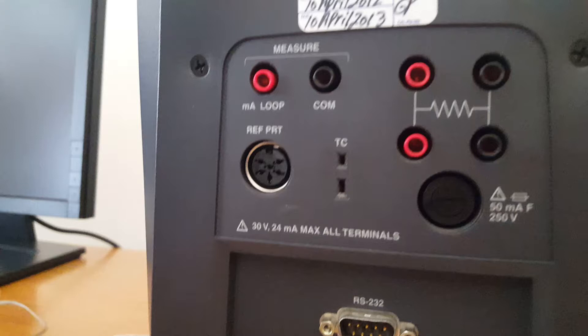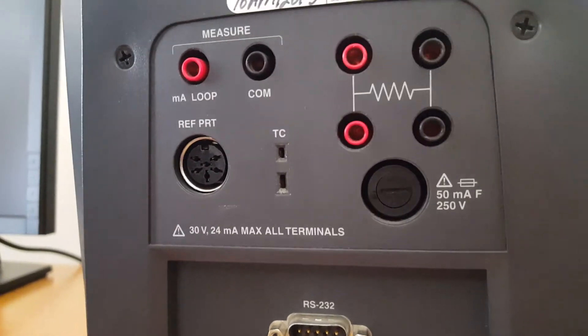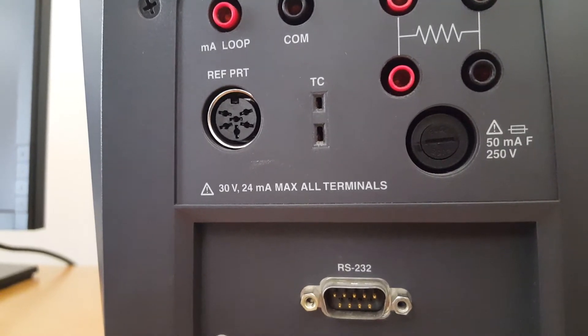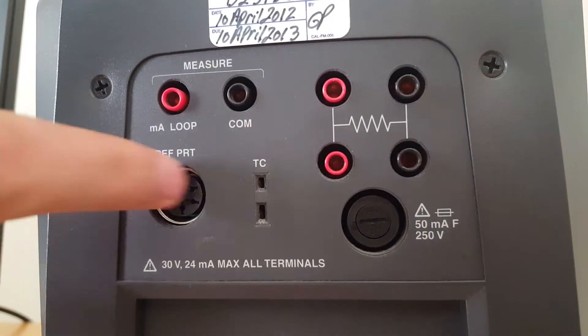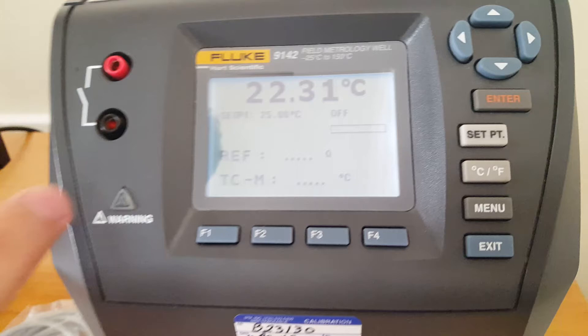About the holes: this one is for the reference PRT. PRT stands for Platinum Resistance Thermometer. We use a platinum resistance thermometer as a reference because it has higher accuracy — it is a type of RTD but with more accuracy. So if we use a reference PRT, we can compare the reference value with the temperature device value. These holes are for thermocouples, the holes above are for multimeters, and these holes are for RTDs.